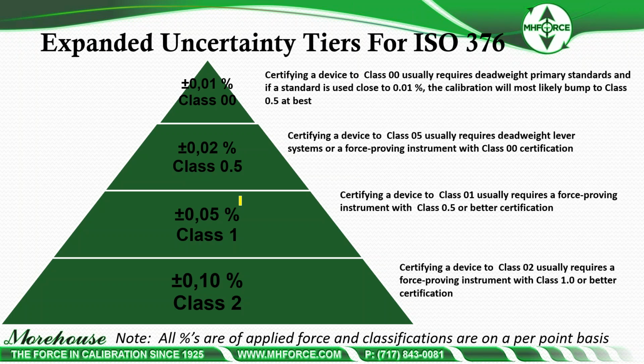Now here's how ISO 376 does it. It's more in line with that metrological traceability and uncertainty. So the plus minus 0.01, if you have an uncertainty of better than 0.01, you can certify a device to class 00, usually requires dead weight primary standards. And if a standard is used close to 0.01, the calibration will mostly bump to class half at best, because there are lots of other things to consider. So the way this propagates is 0.01 class 00, 0.02 class half, 0.05 class 1, and then 0.1 class 2.